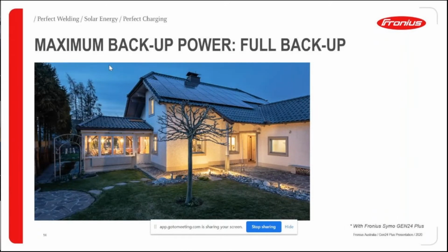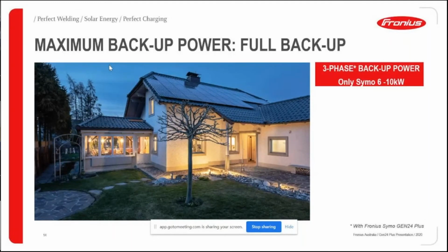So there's still the second option for backup power. With the Gen24s, you can go to what we call a full backup option, where with the bigger inverters, say a Symo 10, you could probably back up the entire house. That obviously depends on the loads in the house, but the Symo 10 is going to supply true three-phase power and can power three-phase appliances and three-phase motors. Obviously, you have to look at the surge capacity of your motors and what they're going to draw, but it is true three-phase backup power with a Symo inverter.